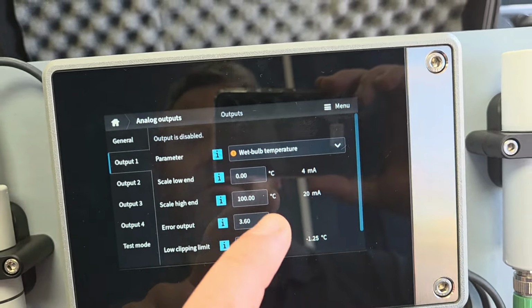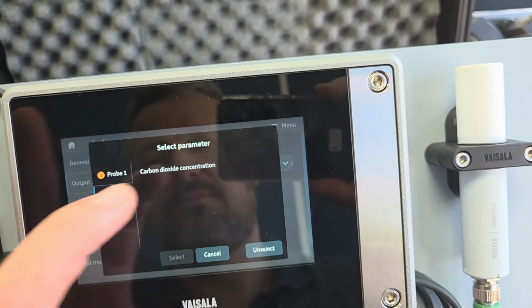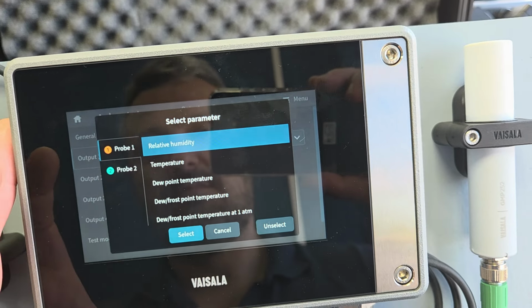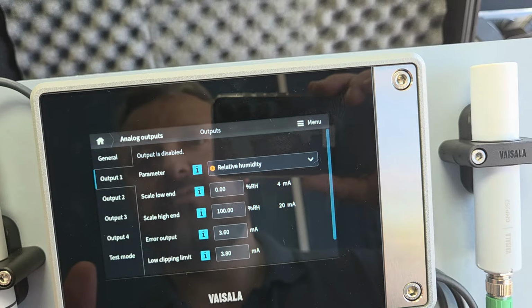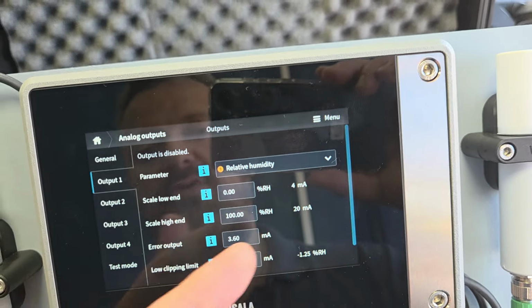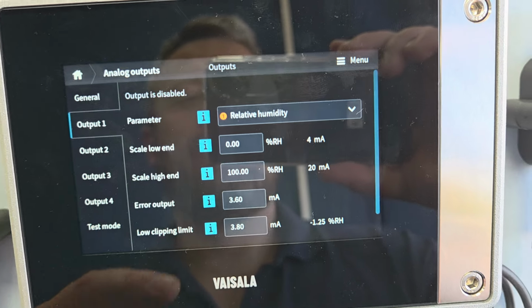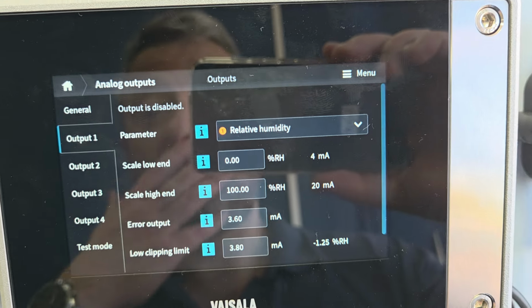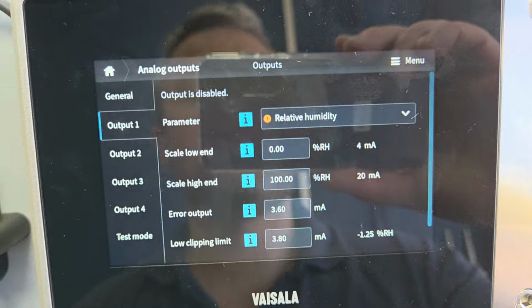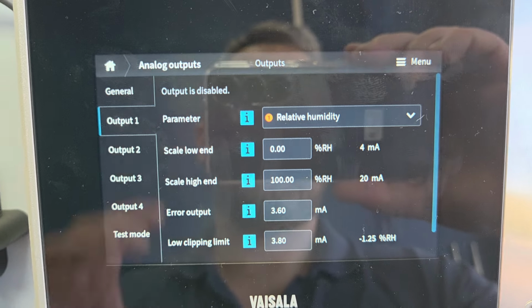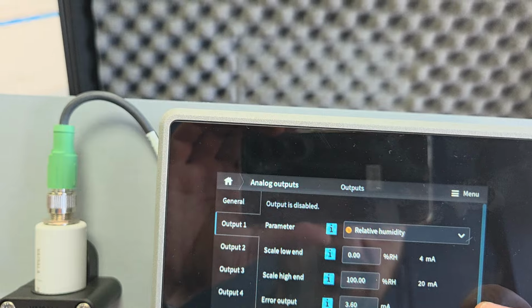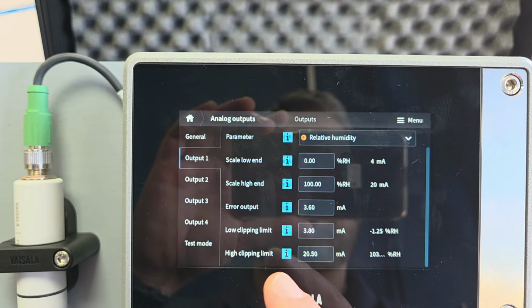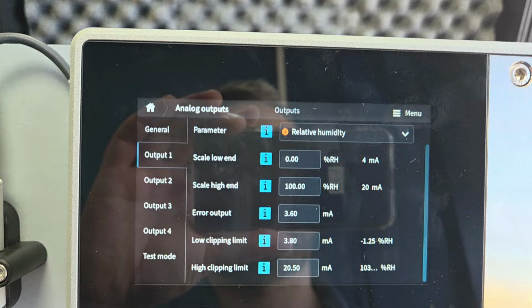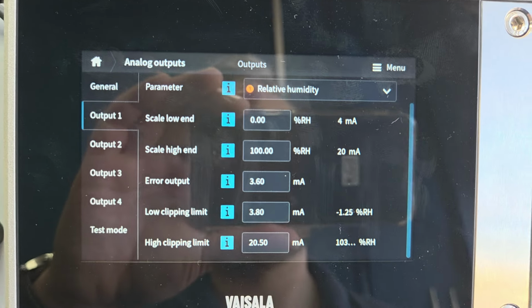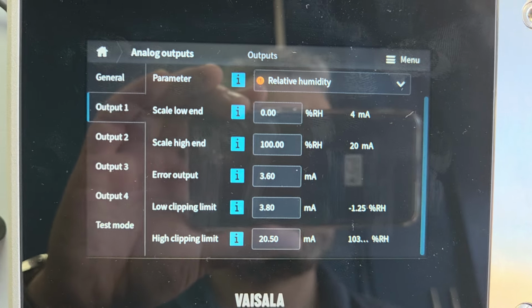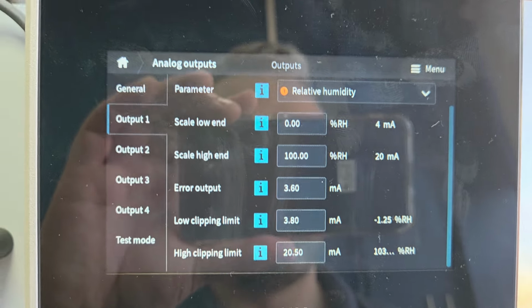Output 1, okay, wet bulb, more likely you would do that as probe 1 RH. If I wanted to put it on low end, 0 to 100%, that seems common, you can do what you want. And then your error output, do you want to go, what do you call it, burnout high, burnout low, what we've picked here. And the low clipping, I think this is actually Namur, low clipping limit and high. So a 4-20 milliamp, 0 to 100%, it would actually read a little bit less than 0 and a little bit more than 100, although that's impossible in this situation.